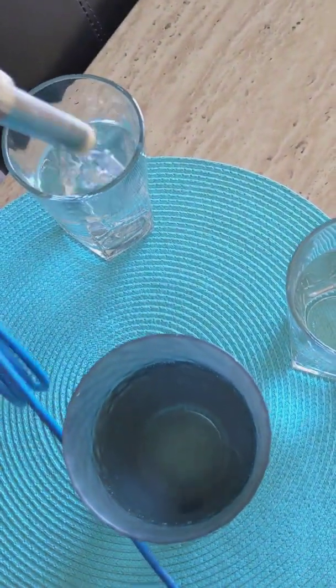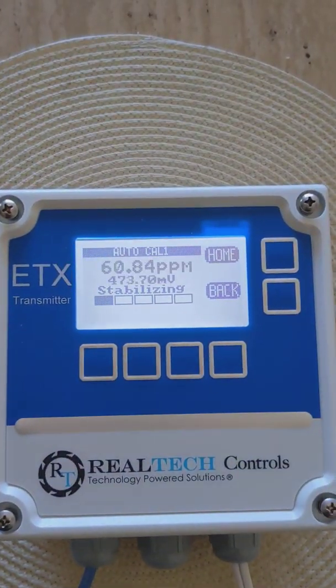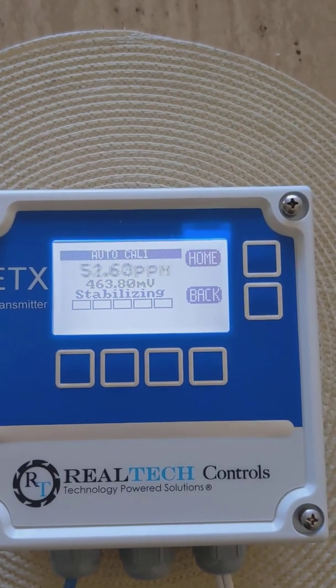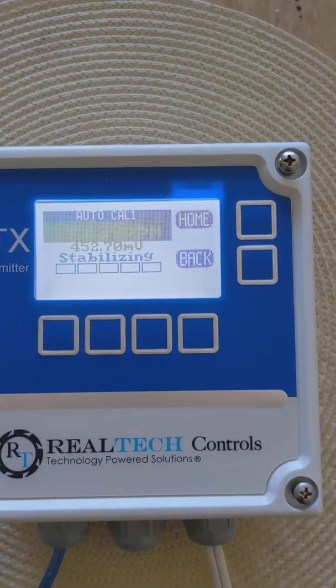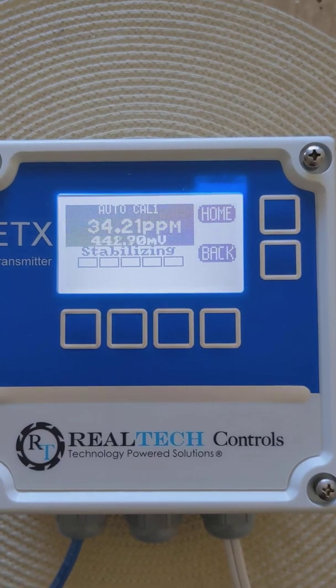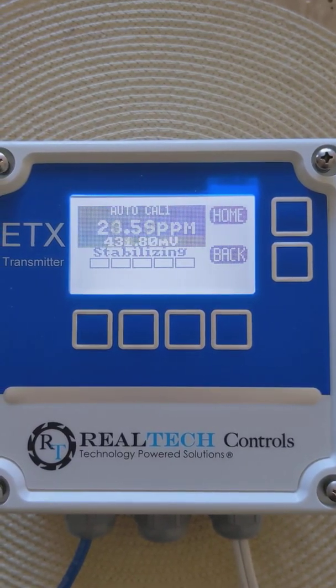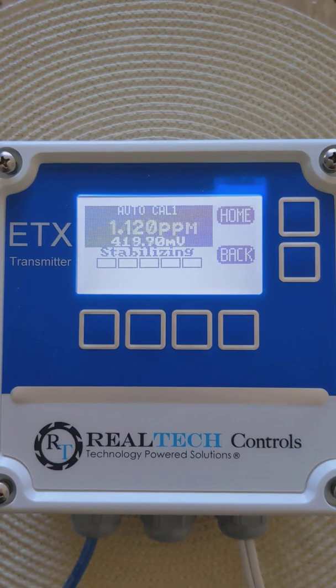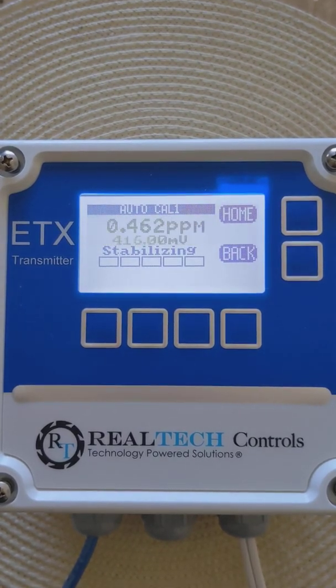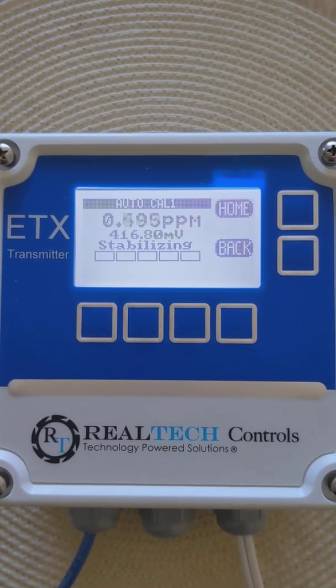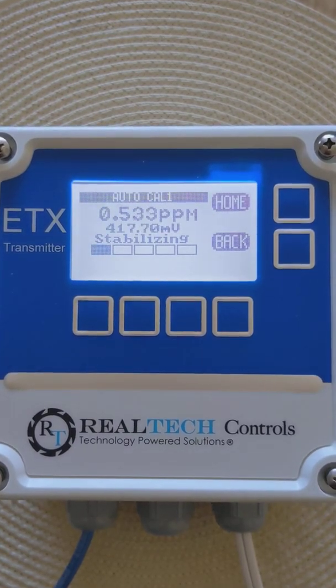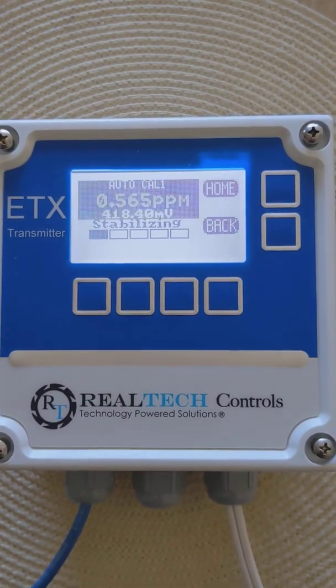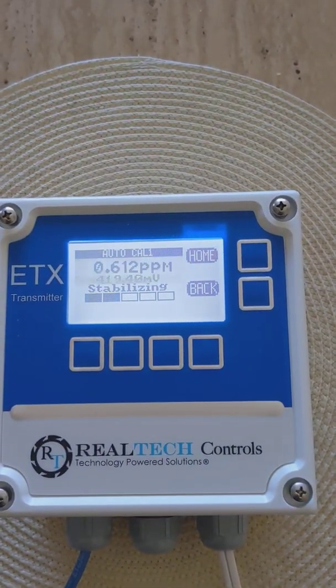And what I'm going to do is I'm going to rinse the sensor again. And I'm just going to put it in the distilled water solution. And you can see it's waiting for it to stabilize. When the bars are all the way to the right on the stabilization, that means it's roughly stabilized. Just have to wait for the controller to recognize that it's a stable value. I'm going to try swirling it ever so slightly just to simulate a little bit of flow.